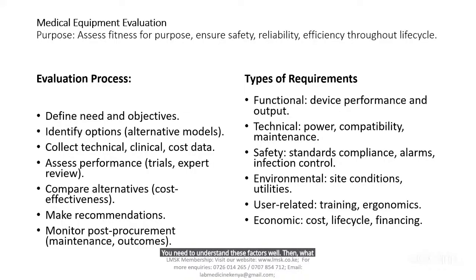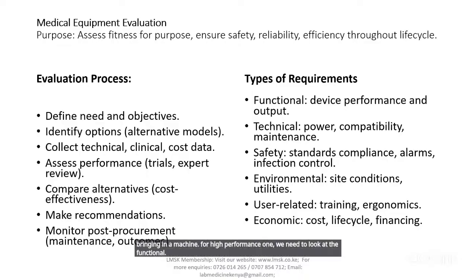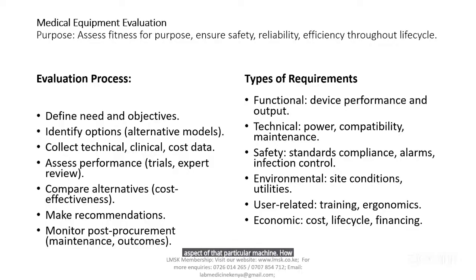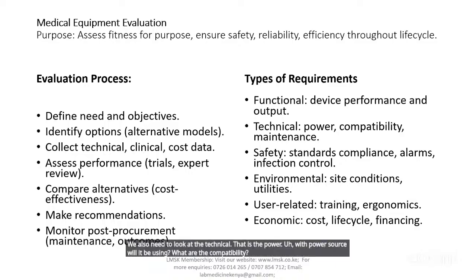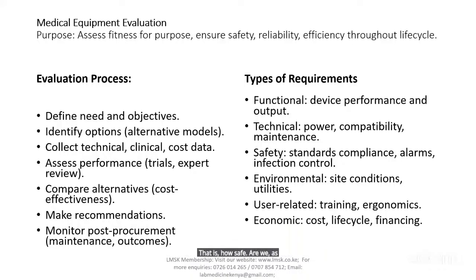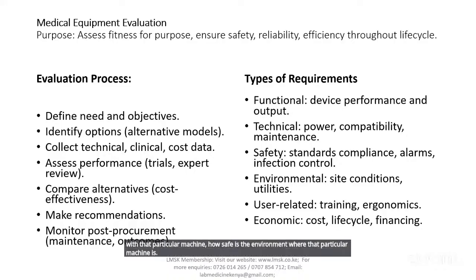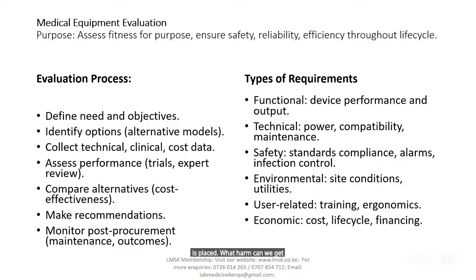Then, what requirements are we supposed to also factor in when we are bringing in a machine for high performance? One, we need to look at the functional aspect of that particular machine. How is it performing? What is the output? We also need to look at the technical, that is the power, which power source it will be using, the compatibility, and also the maintenance. Then we also need to look at the safety aspect. That is, how safe are we as personnel working with that particular machine? How safe is the environment where that particular machine is placed? What harm can we get from maybe being exposed to that machine for long? Those are details that we need to also check on.